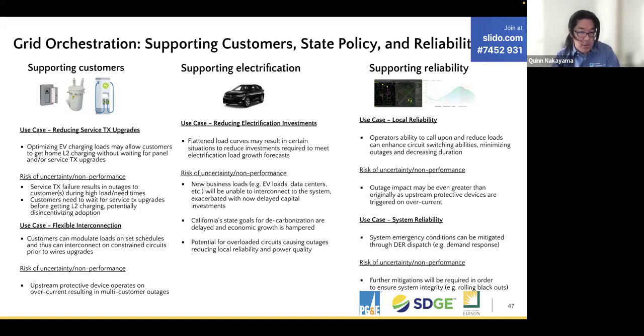But when you peer into it, that constraint may only occur during this particular day, these particular hours, in a particular year. What you can do is set real-time, day-ahead type schedules that say, okay, I know you wanted 4 megawatts all the time, but tomorrow for these hours, if you can just get 2 megawatts and manage through the charging process, we can get you interconnected tomorrow. You don't have to wait for long wires upgrades to enable that capability.